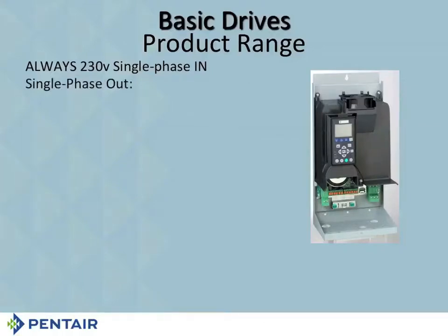Now, of course, you can get single phase out. It's one of the drives where you have the option of single phase or three phase out. So if you put 230-volt in, you can get 230-volt single phase out. If you're going to do that, it must be submersible motors only. This can be used for above ground or submersible pumps, but if you're going to use it as single phase output, it has to be submersible motors.